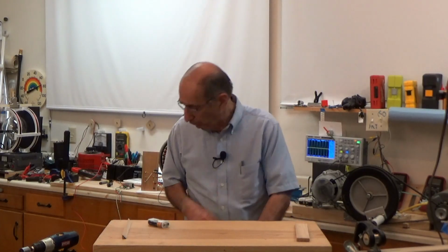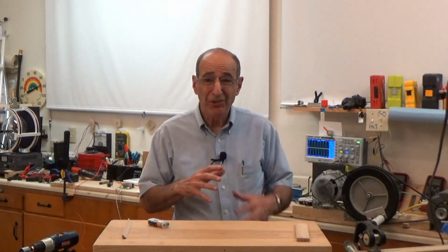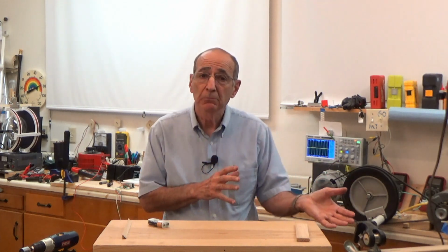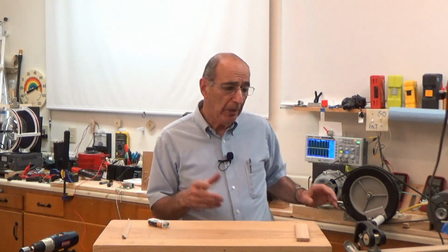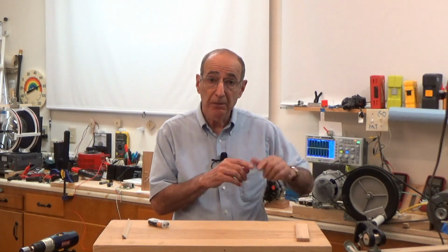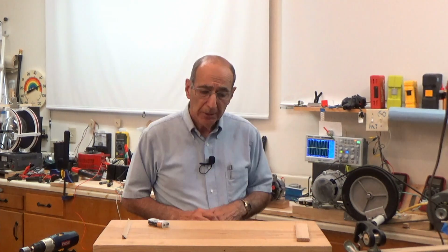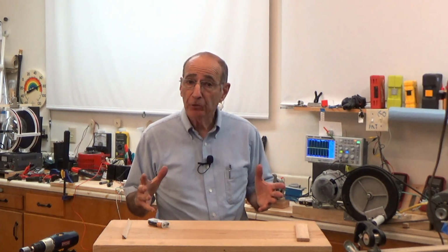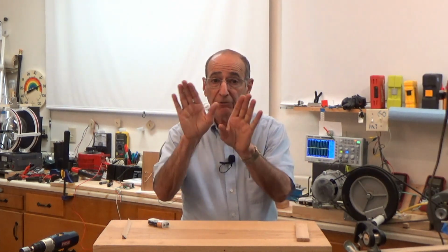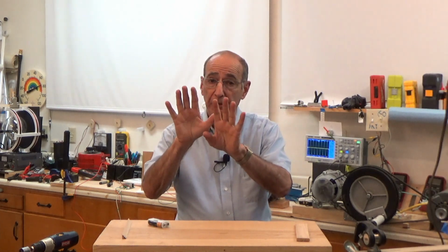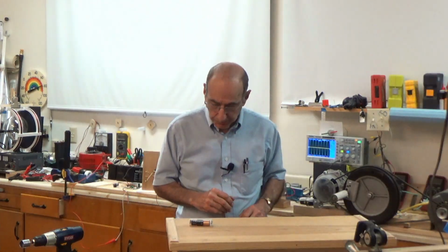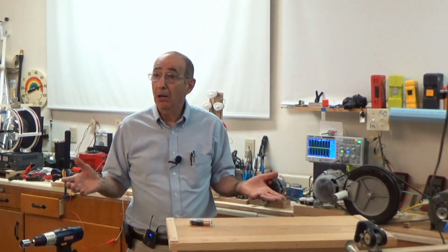Until recently, synchronous motors were not very common. They had kind of niche applications. Factories had them for applications where maybe you wanted a very precise control of speed, didn't want it to change at all. They used the synchronous motor to do some power factor correction, which means if you've got your amps and your volts out of phase, which is very typical in alternating current, the synchronous motor helped bring them closer together. Other than that, it was not common.